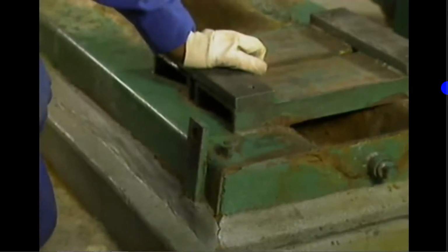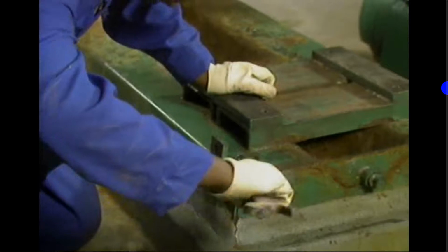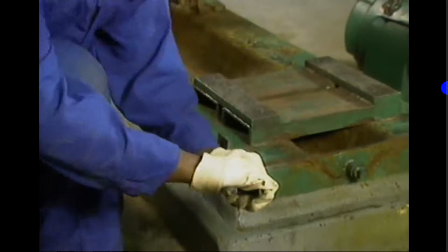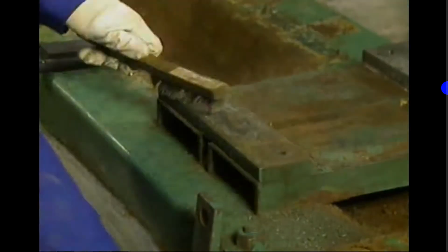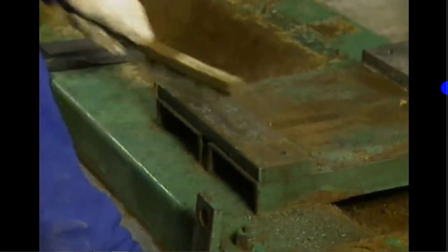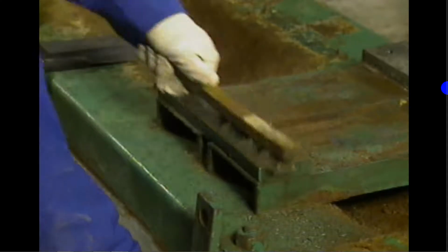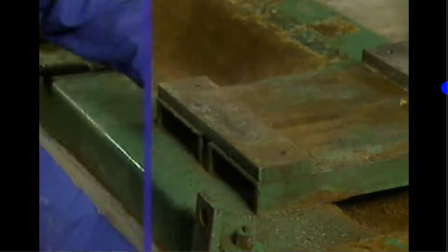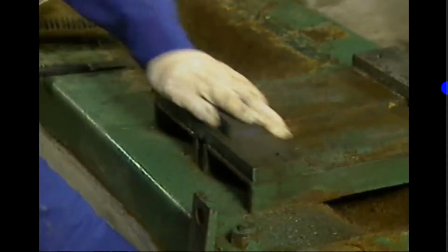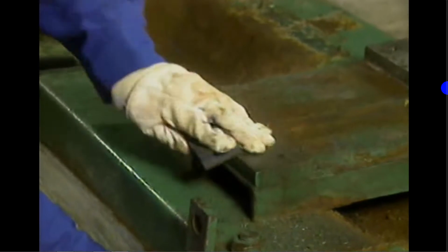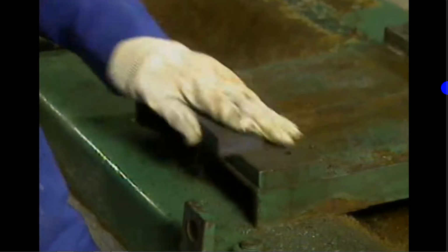If the foundation is concrete or grouted, it should be checked for cracks or loose material that could make it unstable. Also, all anchor or hold-down bolts should be checked to make sure that they're tight and in good condition. The surface of the base plate should be thoroughly cleaned to ensure that the equipment can sit solidly on the foundation. The seating surface, as well as each foot of the equipment, should also be stoned to remove nicks, burrs, or other raised imperfections.